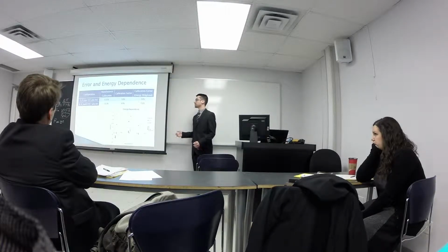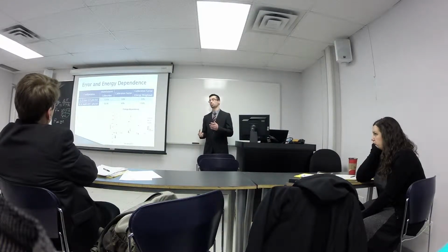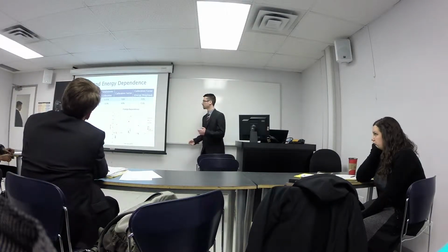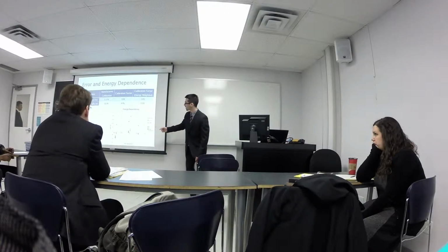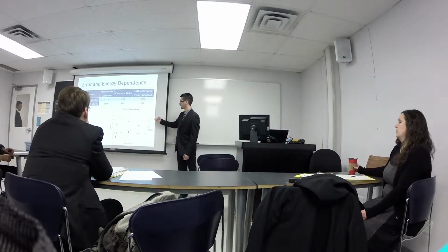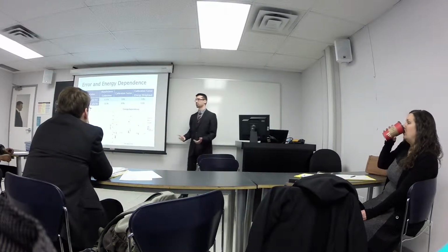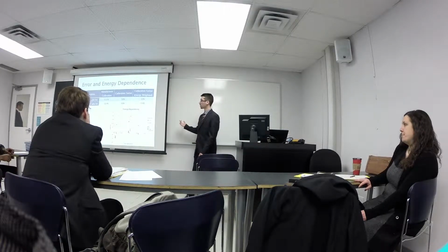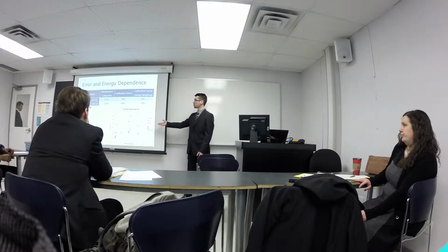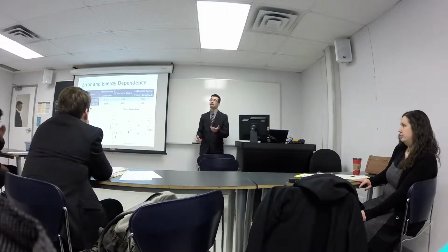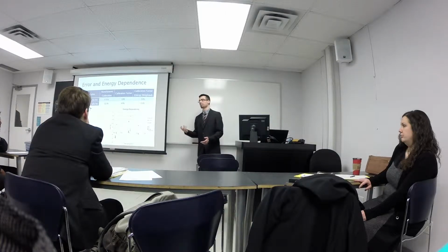This energy dependency graph shows how the detector response changes as a function of the energy from the source, even when you're supposed to be at the same dose rate. Over here we have 1 microsievert per hour, but at different energies, according to the source, there was actually a different response. The dashed lines represent the IEC requirement. After calibration, which are these two colors, you can see that it falls within that, but only at 1 microsievert an hour. At the lower dose rate, it didn't, but again, that was because the measurement time would have to be increased so we'd have better statistics.